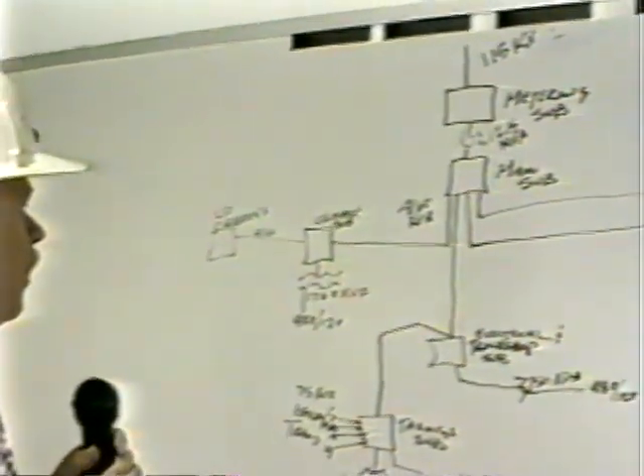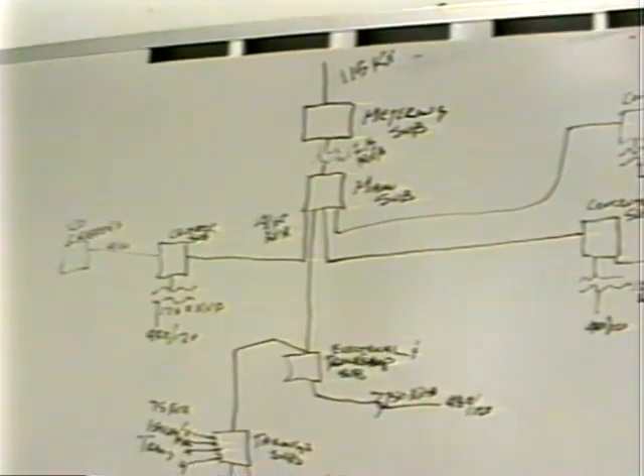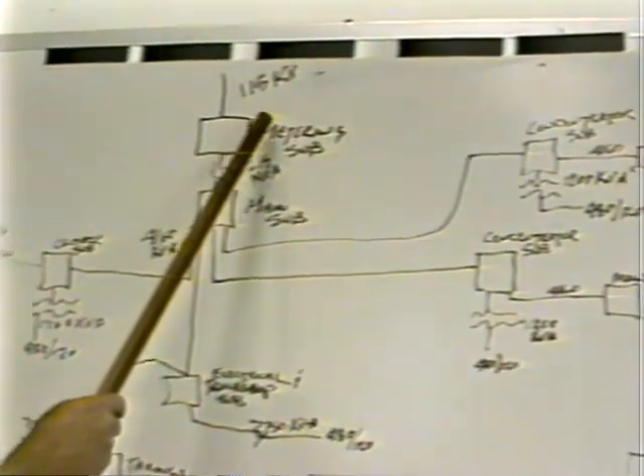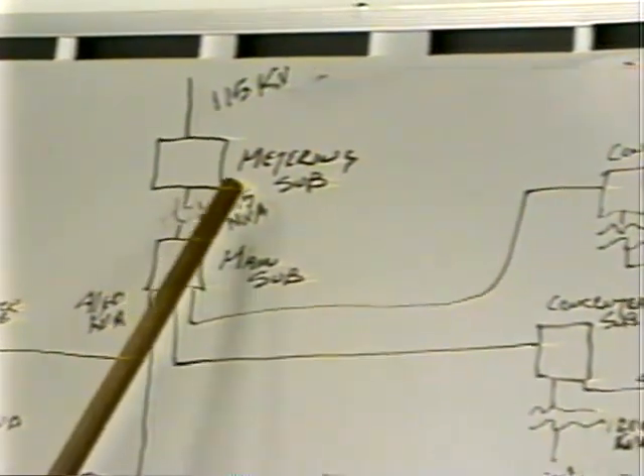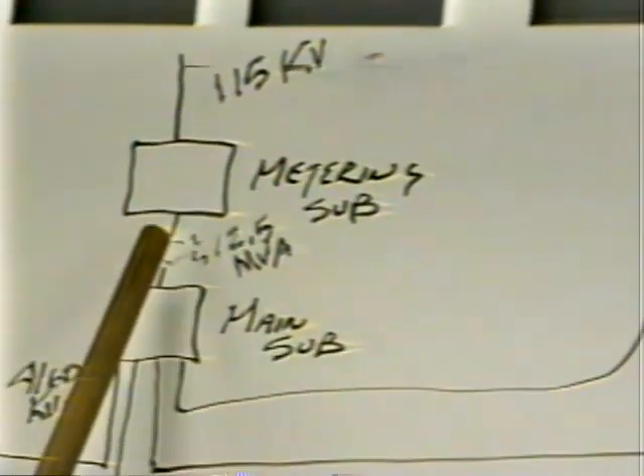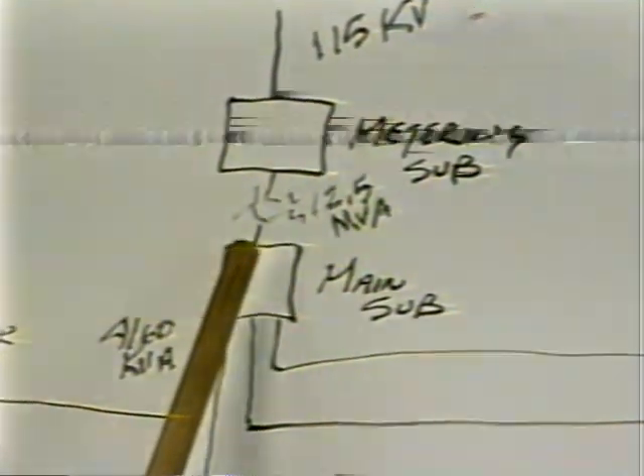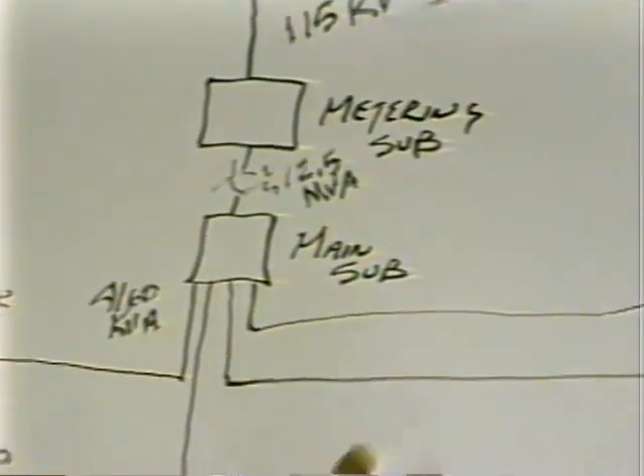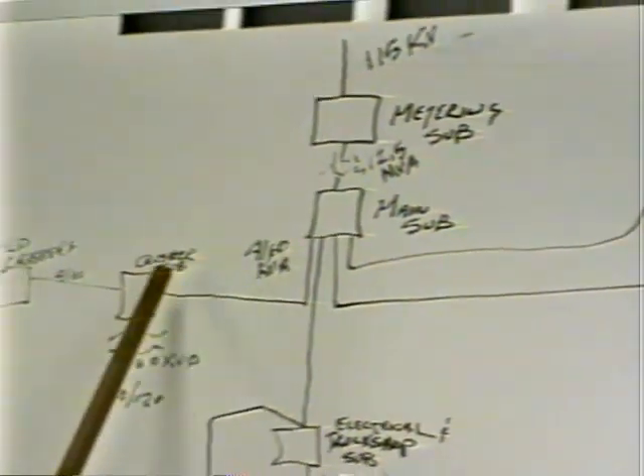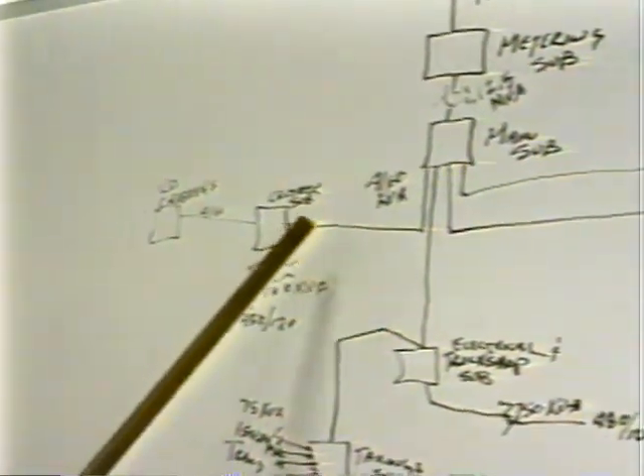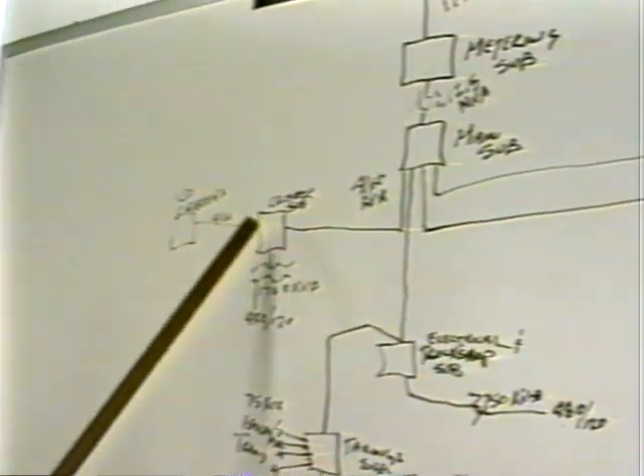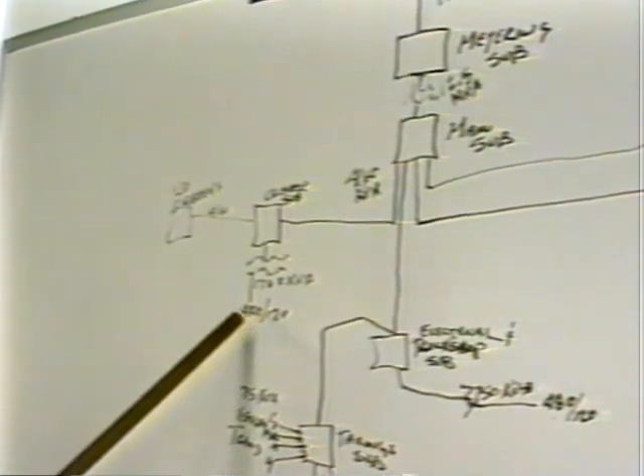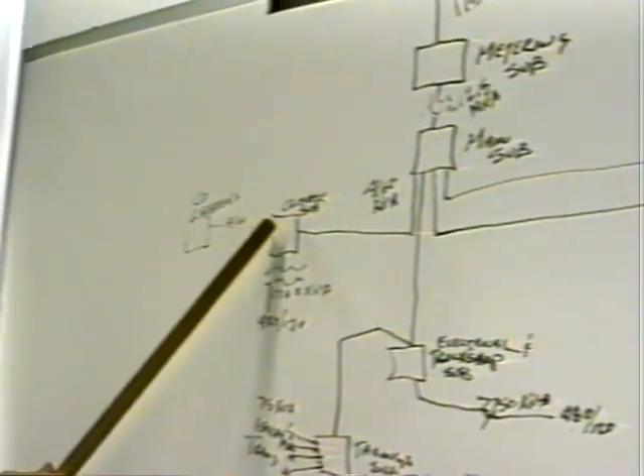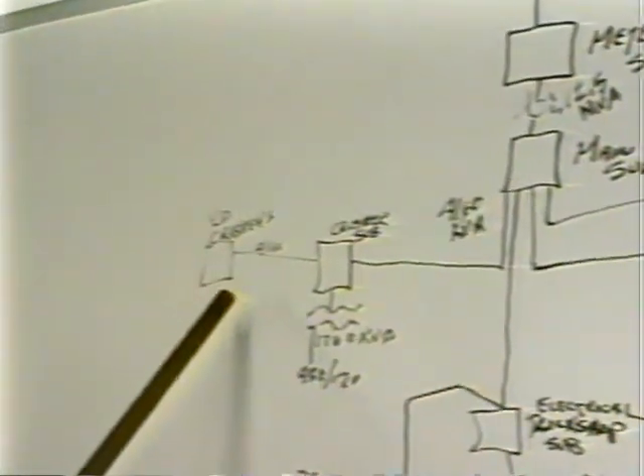Quick overview, I've made up this single line diagram on exactly where our power is distributed from. Primarily we come in, as I said before, on the 115 kV line into the metering sub. Metering sub overhead is taken up and feeds a 12.5 MVA transformer that feeds the main sub. Main sub then distributes 4160 volts in 4 different directions. First place it goes to is a crusher substation. A crusher substation has a 1200 kVA transformer that transforms the voltage down to 480 and is distributed from 480 to 120 throughout the crusher, and then it has 2 4160 feeders that feed the secondary crushers.